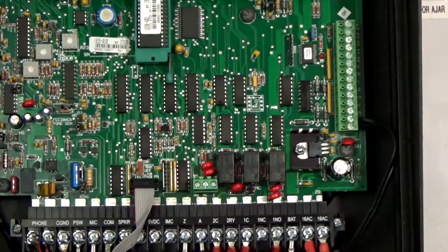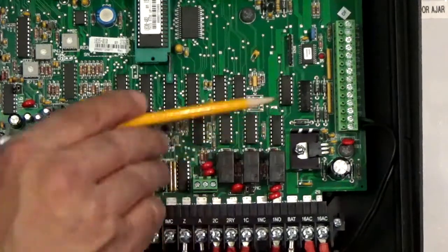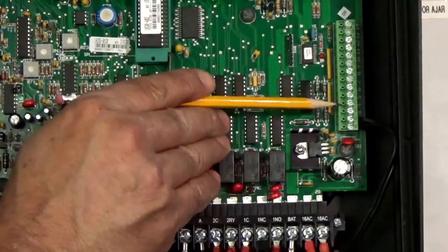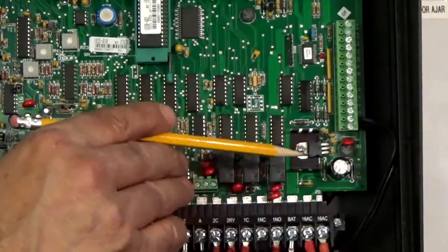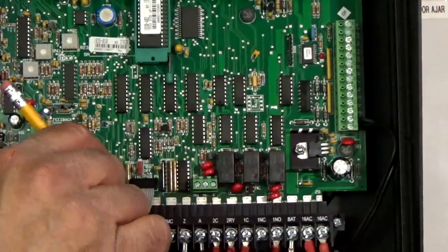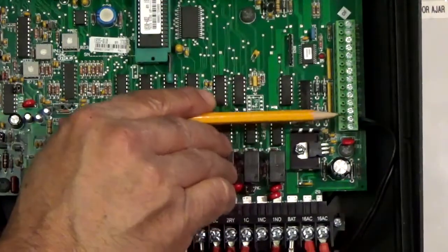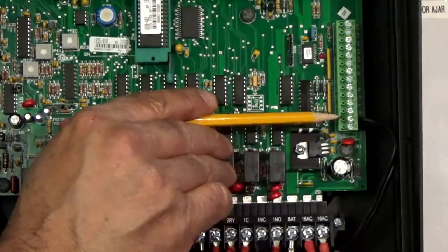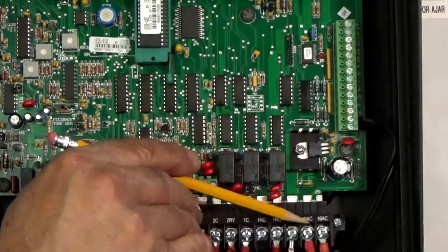Now we're going to talk about some of the requirements before the RS232 test. We've got to make sure that we have power on the auxiliary terminal strip on terminals one and two. Now the board comes with two power supplies, 16 and a half volt VAC, and one is dedicated for terminals one and two, and the other one is dedicated for the main terminal strip. Do not share this power together.